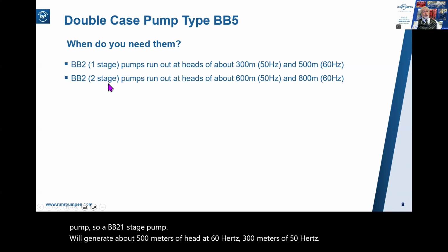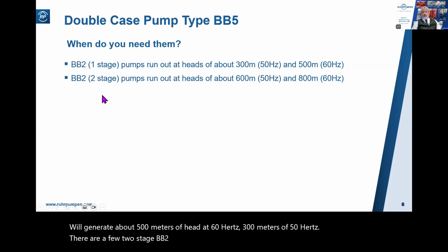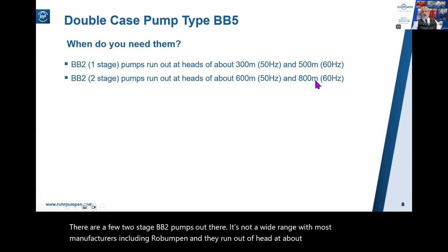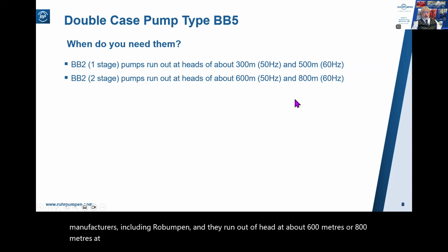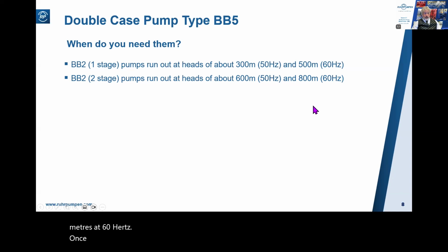There are a few two-stage BB2 pumps out there. It's not a wide range with most manufacturers, including Ruhrpumpen, and they run out of head at about 600 meters or 800 meters at 60 hertz. Once you get above that, you need a multi-stage pump.